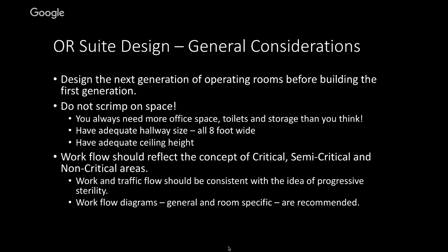One thing that is important to realize is that hallway sizes need to be at least 8 feet wide. Now, that seems to be a waste of space sometimes, but the truth is that a gurney is 7 foot something by 3. And so if you're trying to get 2 past each other in the hallway, or you're trying to store some equipment in the hallway, you need it wider than you expect. And of course, the other thing is that sometimes you have to turn the gurney 180 degrees, and again, need that. The other common mistake is that the ceilings are too low. As a general rule, 10 foot is the bare minimum that you should have.